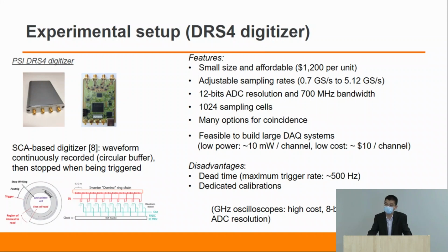The sampling rate is between 0.7 gigahertz and 5.12 gigahertz, and the sampling rate can be adjusted. The ADC resolution is 12 bits, which is a very nice feature for gigahertz digitizers, and the bandwidth is about 700 megahertz. The number of sample cells is 1024. This means you can have about a 200 nanosecond time window, even using a sampling rate of 5 gigahertz. So you can get the rising edge of the pulse as well as the falling edge of the pulse.